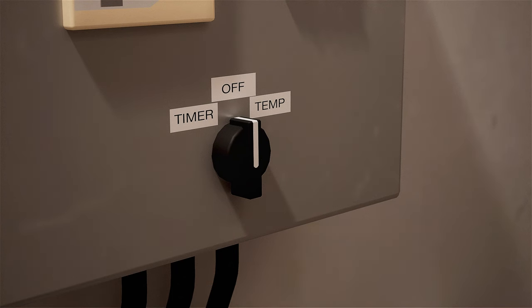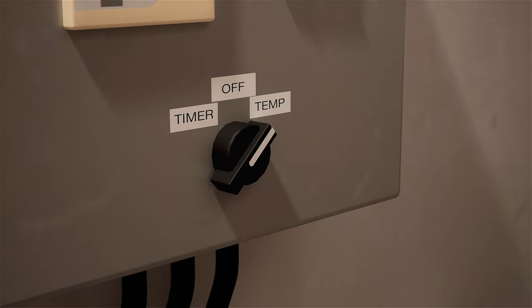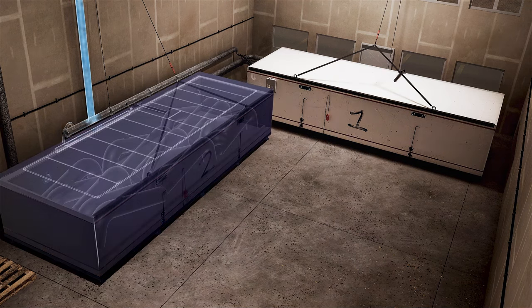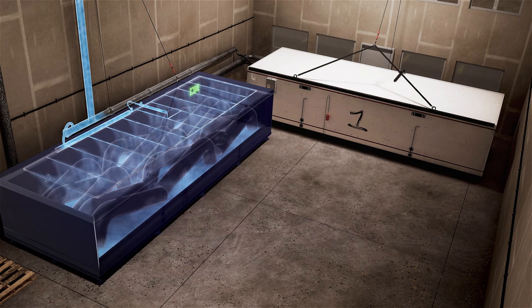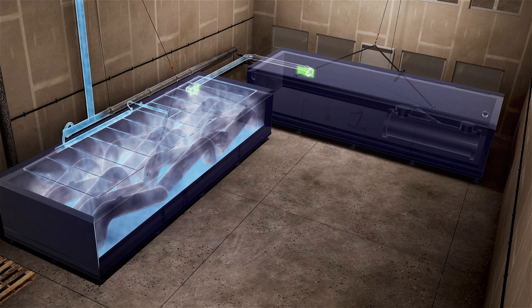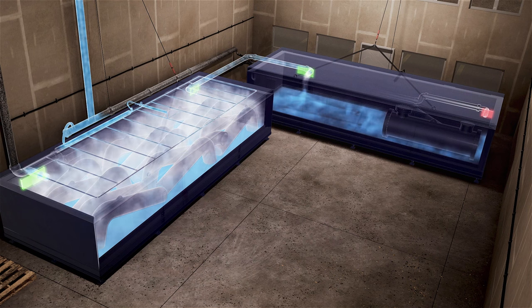Later that morning, the additional nitrogen cooling cycle was initiated in Cooler 2. However, the position of the gate valves was not adjusted to support this additional cooling cycle. This left an open flow path from Cooler 2 to Cooler 1. But with Cooler 1's exhaust gate valve closed, the preferred path of nitrogen was through the open exhaust duct on Cooler 2.